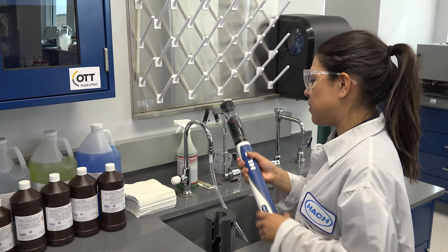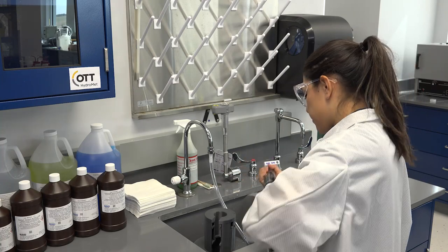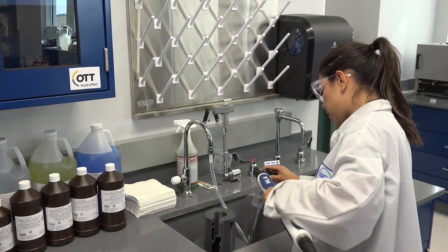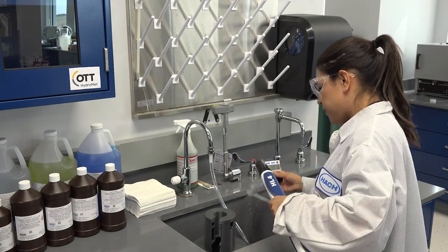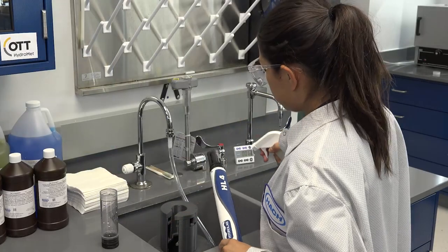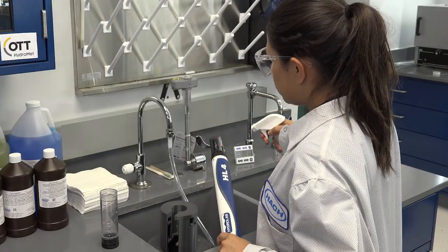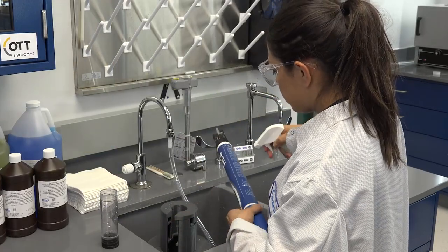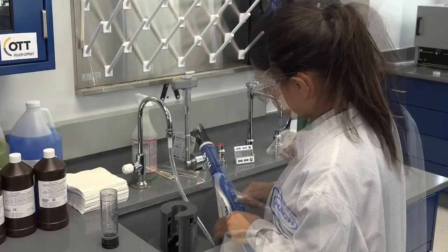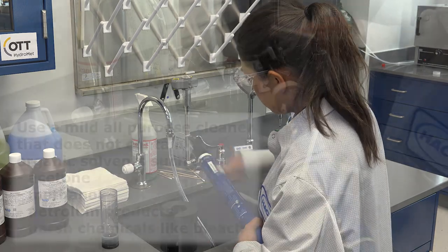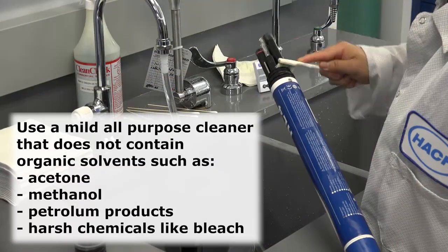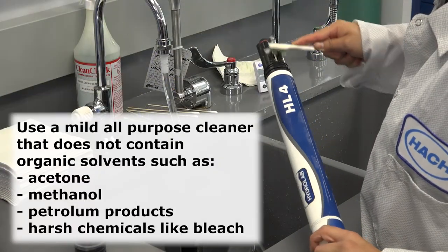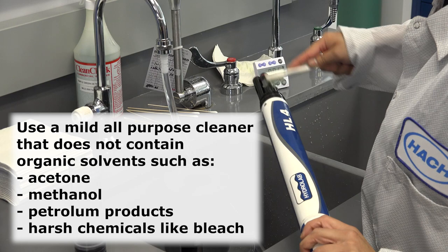The conductivity sensor should be regularly cleaned because debris, organisms, and other contaminants in the sensor cell will have a negative impact on the accuracy and stability of the readings. If deposits on the sensor are difficult to remove, soak the sensor in warm fresh water until the deposits soften.